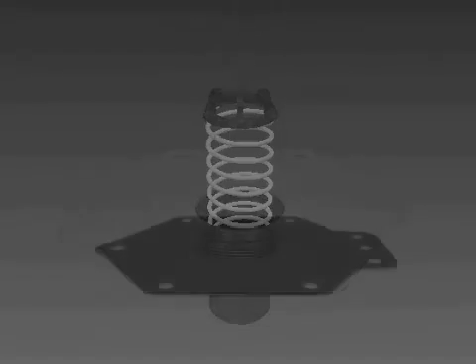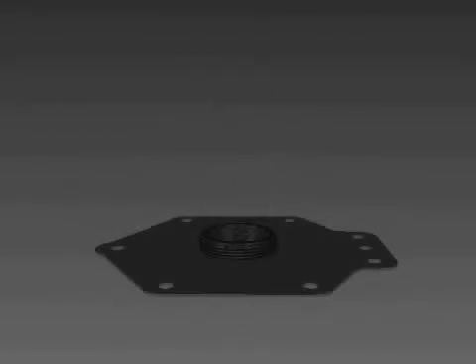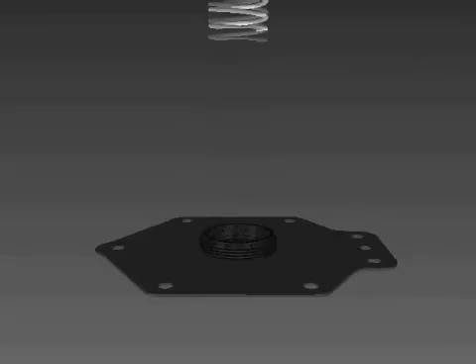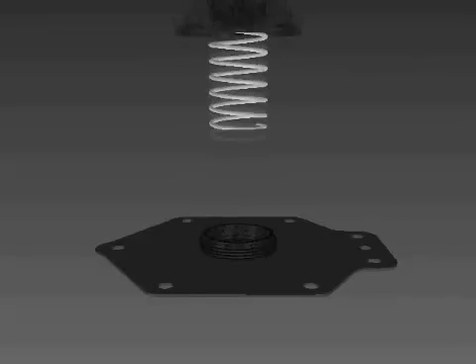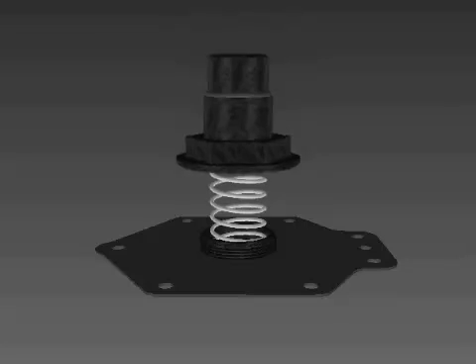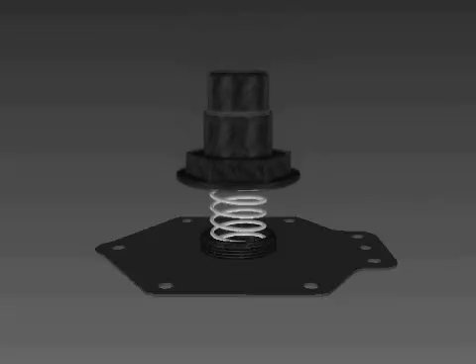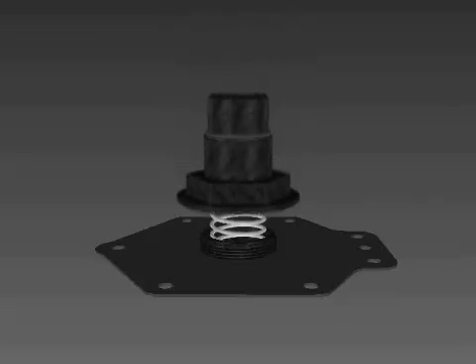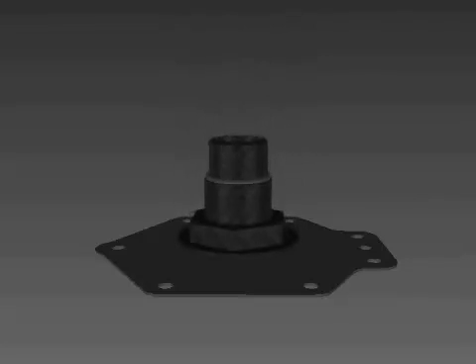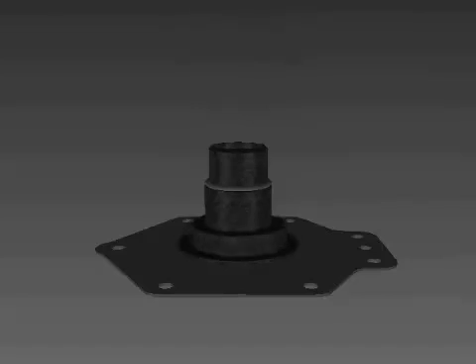To reassemble, place the seat face down in the palm of your hand with new diaphragm around the threads. Place seat guide into seat, cross first and round end toward the spring. Place the spring in the plunger. Push plunger and spring into seat and compress spring and thread the two together. Tighten the seat into the plunger with wrenches so the two parts seal against the diaphragm.